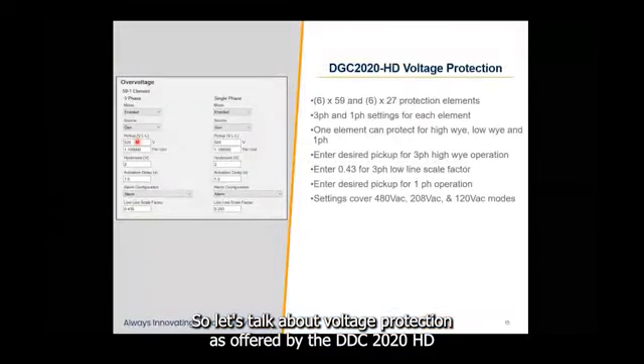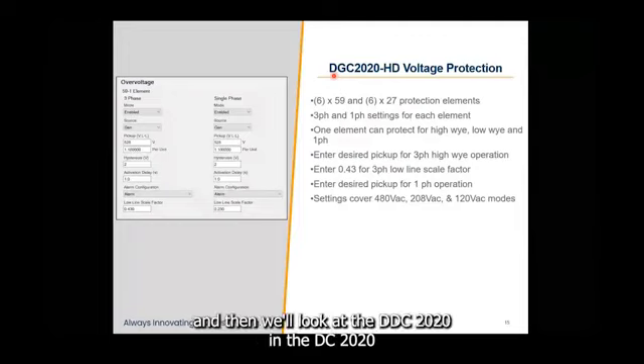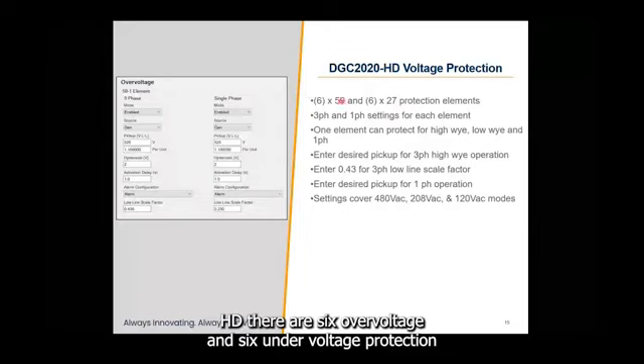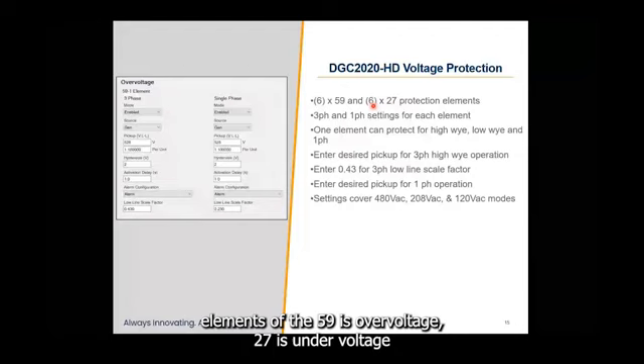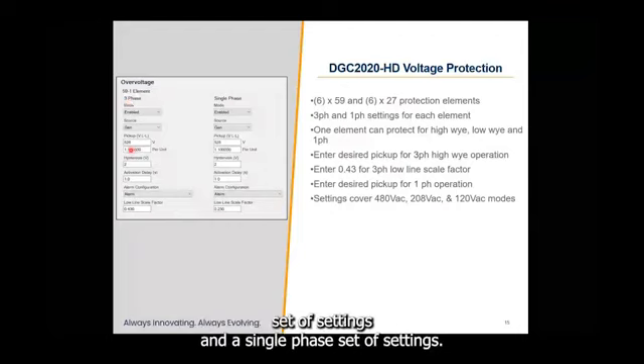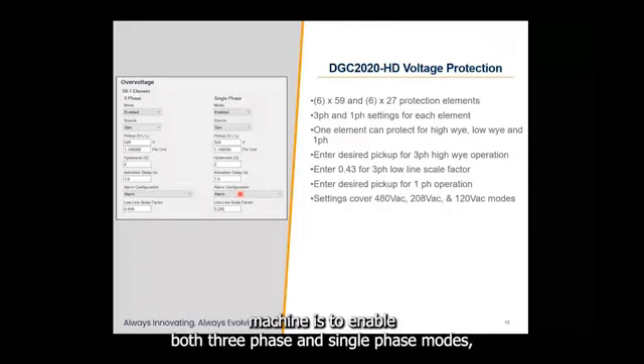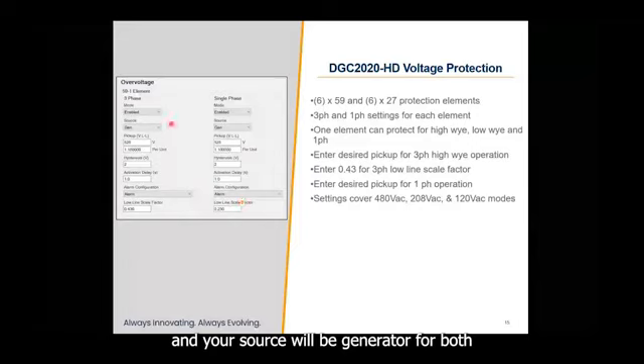So let's talk about voltage protection as offered by the DGC2020-HD, and then we'll look at the DGC2020. In the DGC2020-HD, there are 6 over voltage and 6 under voltage protection elements. So your 59 is over voltage, 27 is under voltage. Each of these elements comprises a 3-phase set of settings and a single phase set of settings. The way you would do this for a 480 volt machine is to enable both 3-phase and single phase modes, with your source as generator for both, and just set the same pickup level.